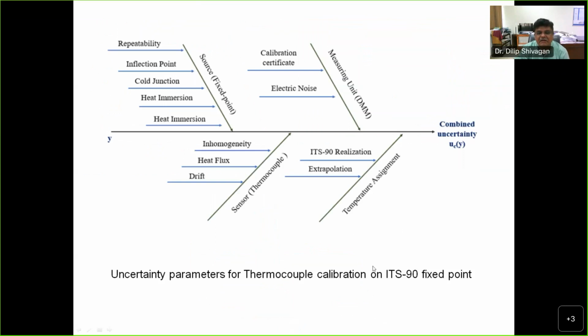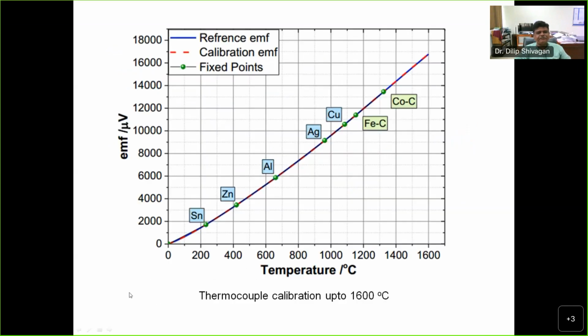Again, like the resistance thermometer, here the difference will be because of the measuring unit, because the voltmeters will have certain electrical noise if your AC is switching on and off, or for the sensor part it is inhomogeneity, which is a very dominating factor, and the drift. Many people in the lower range tend to measure the thermocouple with respect to the SPRT. SPRT has a very good uncertainty, but the required uncertainty due to the thermocouple needs to be taken into account. Although your digital display shows very good values, the background doesn't always repeat. So with this you can have traceability for very high temperature.